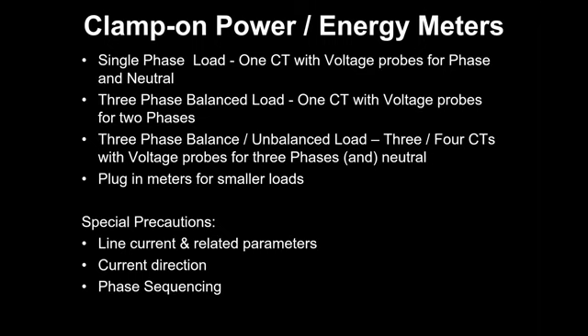So this is more accurate because it is measuring all the parameters, all three phases' current and all three phases' voltage. But it is more expensive. It is more tedious to connect. These are available, I think, from 50,000 rupees to 10 lakhs, depending on what kind of measurement you're doing. Because here, when you are buying this, you always look at the sampling rate, because how many readings it will take per minute or per second. A normal standard meter is available which will measure the data every second. So you'll have data values for every second of time. Now that is sufficient for most audit measurements.